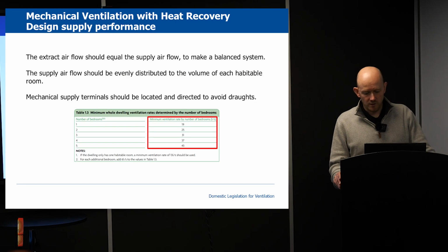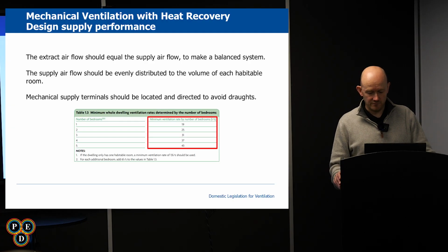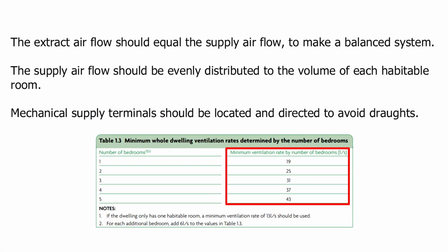The total supply airflow rates should equal the total extract airflow rates. This will allow the system to be balanced, meaning the amount of stale air extracted from the wet rooms is replaced with fresh tempered air into the habitable rooms. This applies to both continuous rate and high rate. This needs to be achieved by proportional distribution of the airflow into each of the habitable rooms.